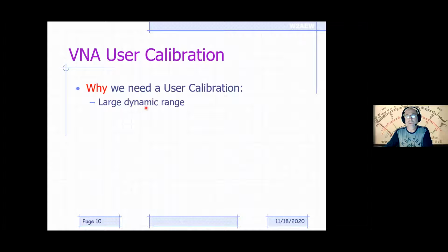So what that means is that any little nonlinearities or issues in the analyzer itself or due to the setup can affect the ability to make those very large dynamic range measurements. So part of the calibration is to measure any of those imperfections and remove them from our measurement. Another piece of it is that because we need to measure phase, we need to do a calibration. Because remember what I said phase was? Another way to think about phase is that it's a measure of delay. So the longer transmission line, or piece of coax, you have between the instrument and your device, the more phase delay you're going to have.